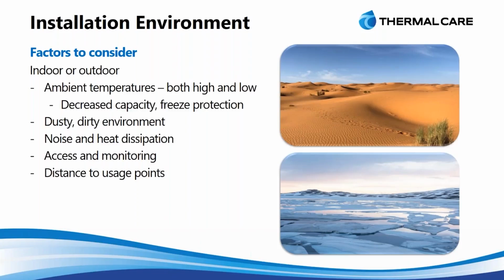From the low side, it's where we talk about the glycol mixture to protect that fluid. Because even if I'm operating at a 50-degree set point, which technically wouldn't require any glycol, I'm still sending that water outside. In winter there's a possibility that water could get trapped out there if there's a power loss or something, and then it could freeze and damage the equipment. So those are some key things to consider for indoor and outdoor.